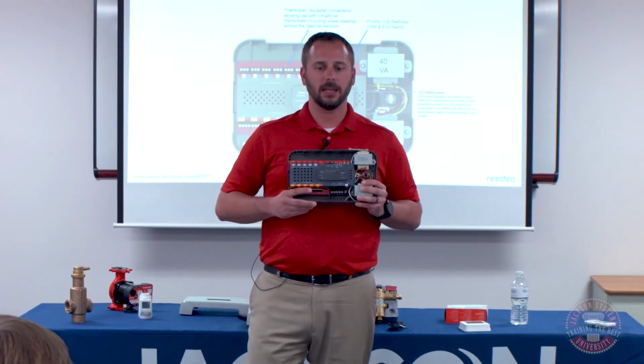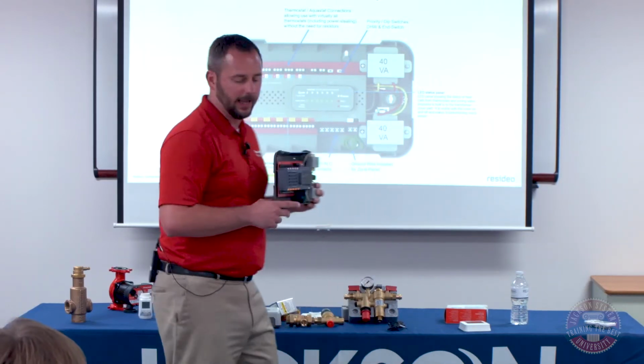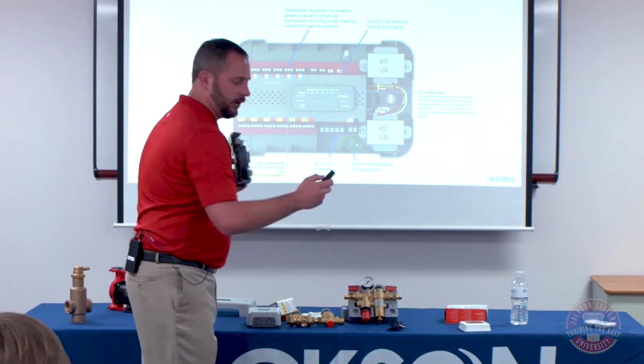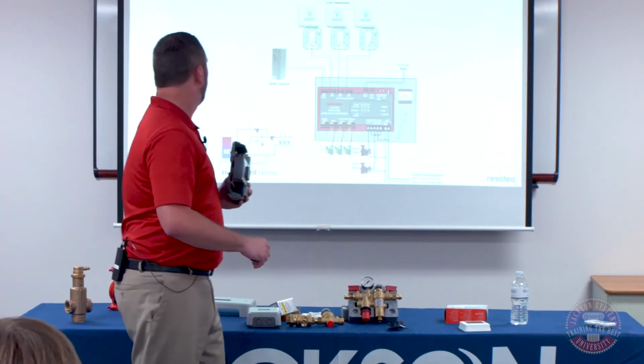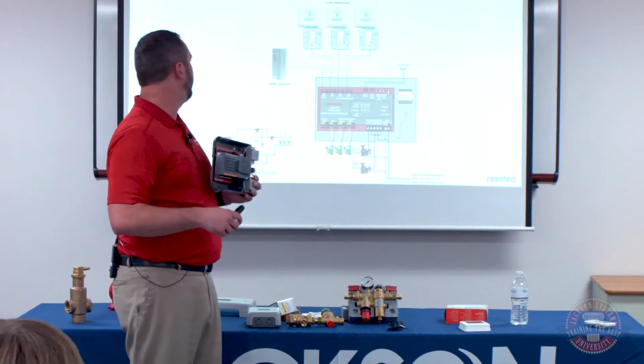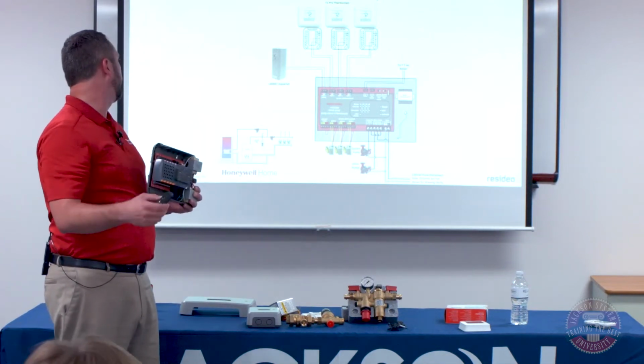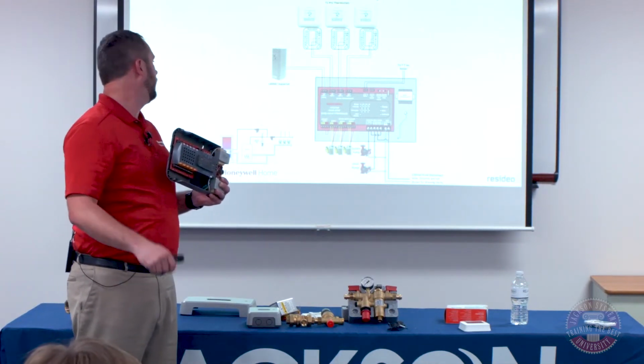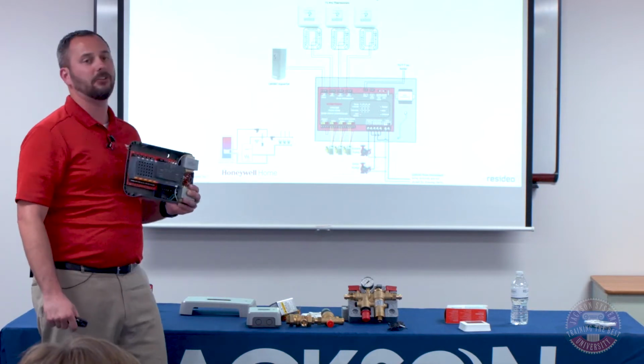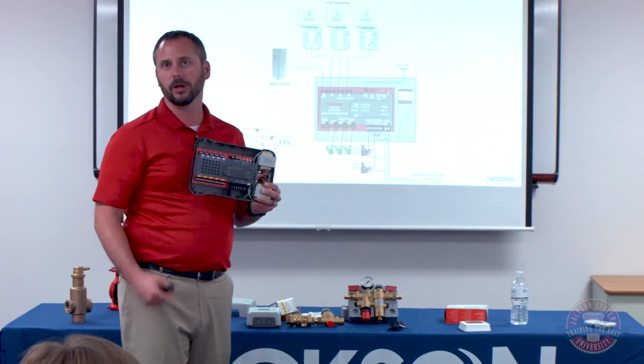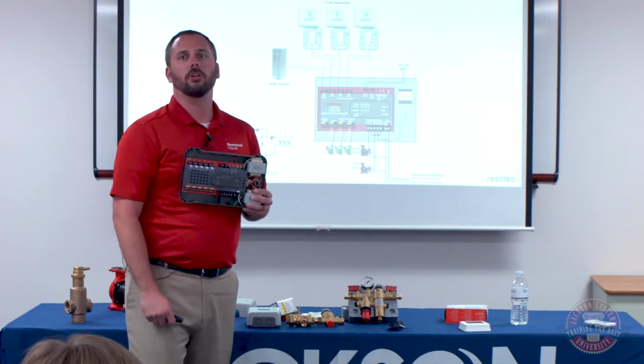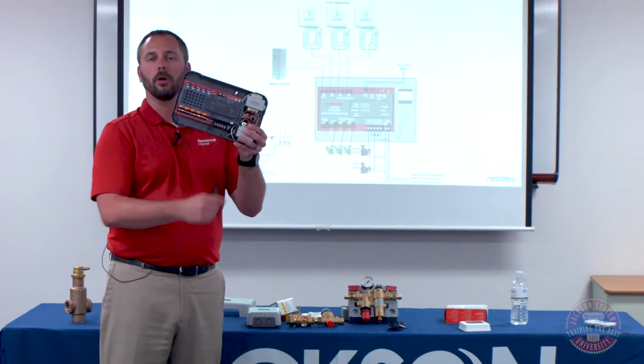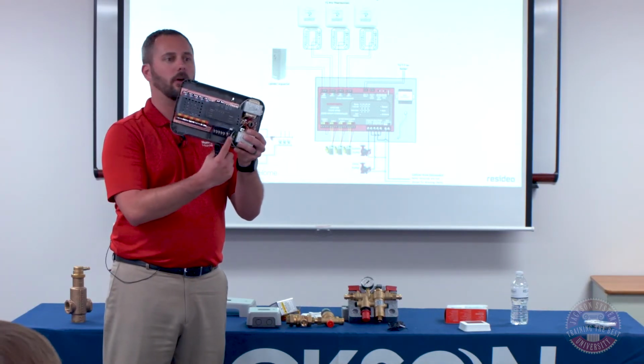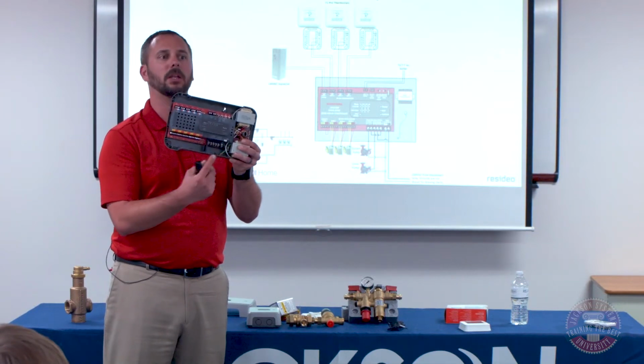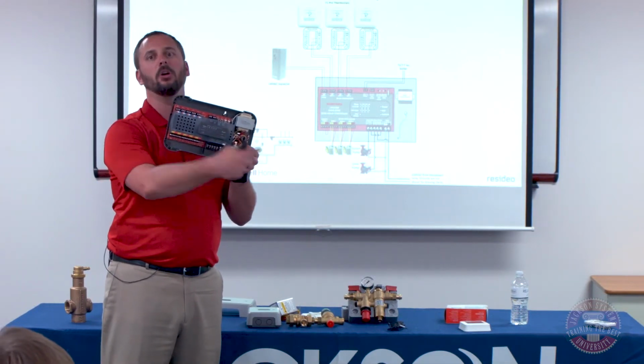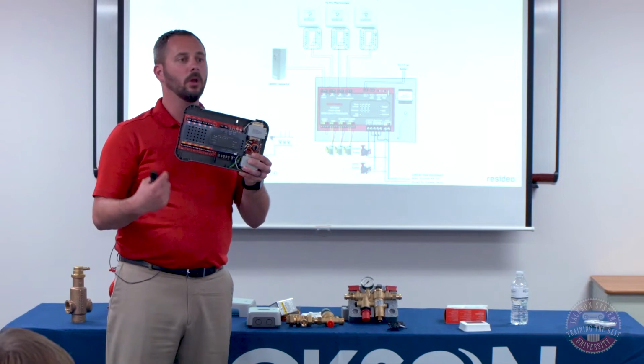Most of the modulating and condensing boilers that exist today, and I've got a couple of diagrams here. So in this example, down in the bottom, you'll see I've got a boiler with an indirect water heater, and this is very typical of a cast iron boiler or a copper fin boiler. So what you're going to do is you're going to wire the pumps into this board. So when there's a call for heat, you need to turn a pump on, you need to turn a pump off, depending on what's calling. Is it the indirect water heater, or is it a system?